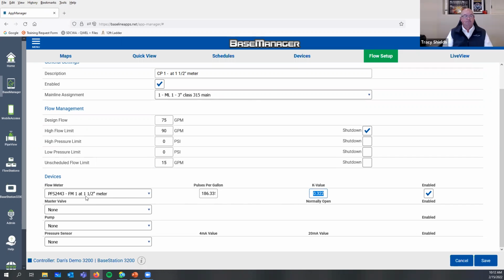So the K value now is going to translate those pulses into GPM. And that comes with our pre-programmed baseline flow sensor. Now, Tracy, if I didn't have a baseline flow sensor, I've got to pull it out and put a new one in because I need to get that. Is that accurate? Yeah, that's accurate. Because the controller doesn't know unless it's a baseline sensor what that K value is. Well, you would have to go to the manufacturer book and take the specs and find the K value and offset. So the takeaway is, if you add your own flow bicoder because you have an existing flow sensor, you're going to have to put your own K value in. Correct. Okay.